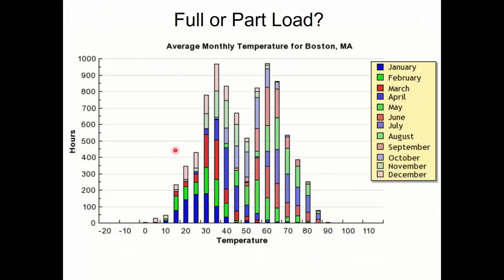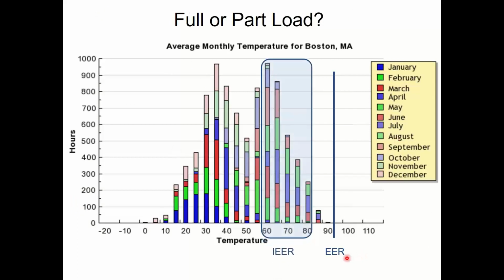So why is part load important? This is why part load is important. EER is for a 95-degree day, which statistically doesn't happen in Boston. I mean, it might happen on occasion, but statistically, no. I have almost no hours there. I have very few hours in the 90s for that matter, right? Whereas I'd love to be awesome and efficient at everything in this blue box. If I can get all those cooling hours right, that's a couple thousand hours of operation. Whereas if I get things really awesome and efficient at 90 degrees, it's only tens of hours of operation a year. It's not super exciting. So I want to be more efficient here. It's a better point for me to care about energy efficiency as well as helping out that dehumidification we talked about.